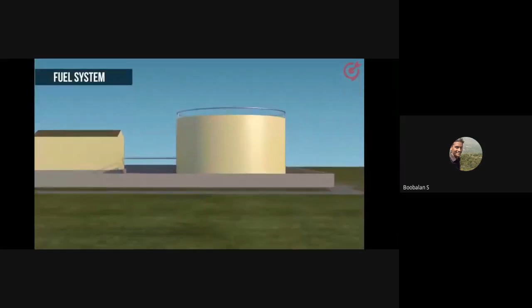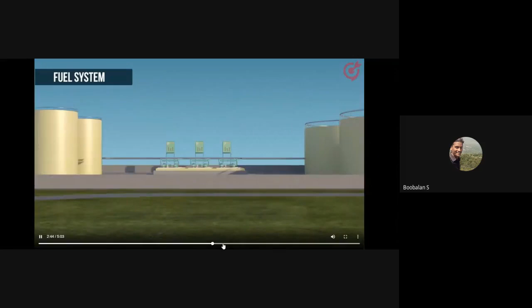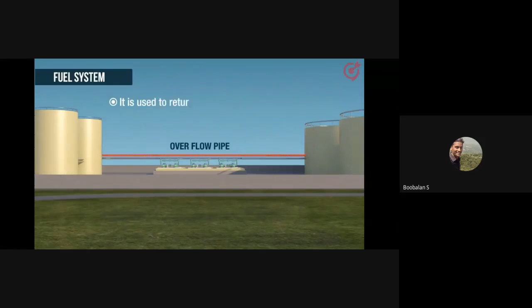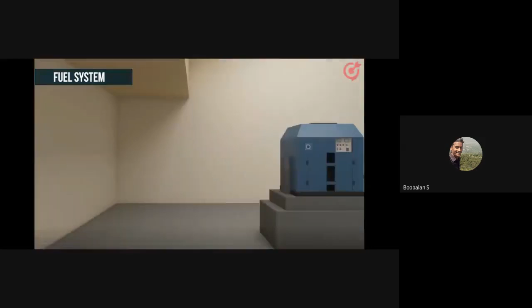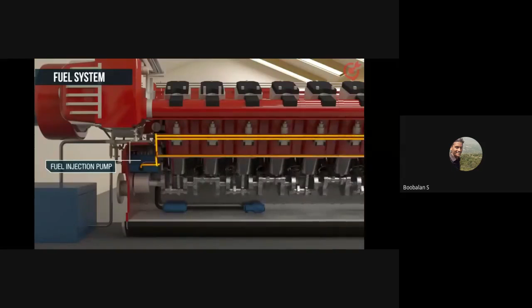The fuel system consists of a storage tank, or main tank, to store the fuel. A transfer oil pipe, and another pipe called the overflow pipe, is available to connect the day tank to the main tank. It returns the oil from the day tank to the main tank in the event of oil overflow. The fuel injection pump injects the fuel from the day tank into the engine cylinder at a high pressure of about 100 bars.